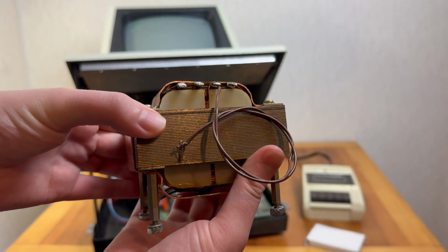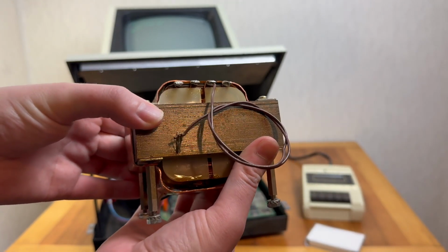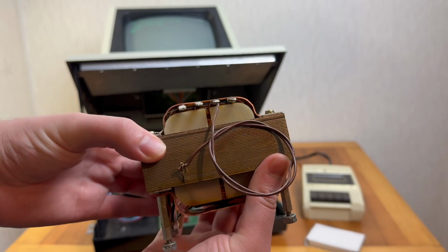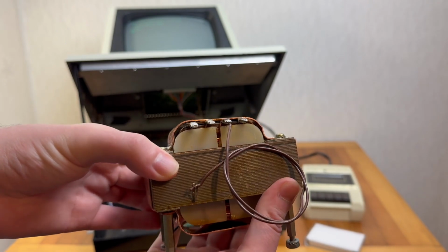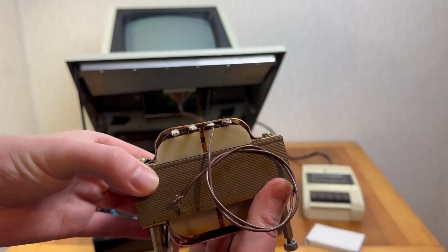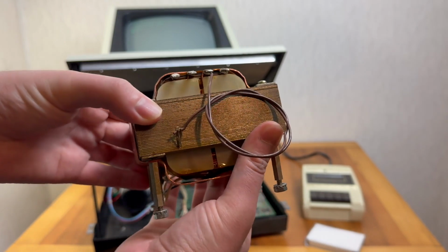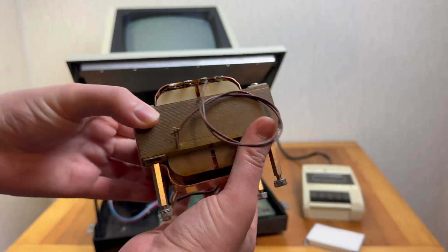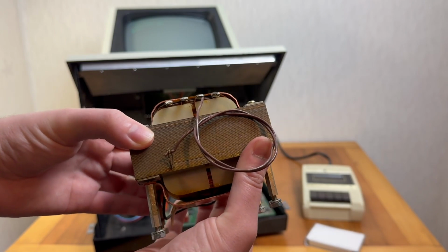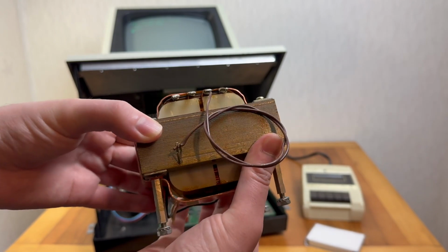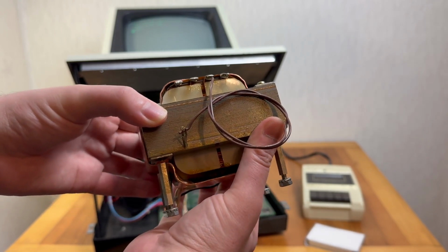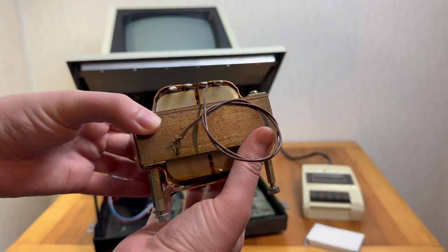This is that original transformer. The PET uses this to step down the incoming 117 volts to the appropriate lower levels required for the various components on the machine. Now, transformers are usually configured to cope with a particular frequency of operation, and this was designed for a 60 Hz system in the US, but was being used on a 50 Hz power supply.